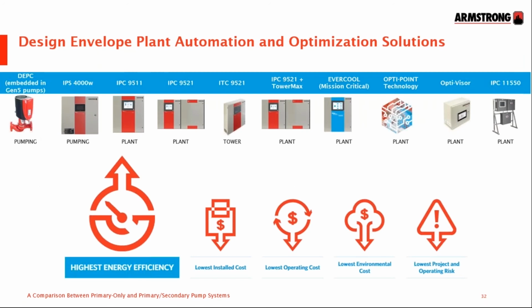Armstrong's range of control products starts with our Design Envelope pumps with the Design Envelope pump controller, which provides sensorless speed control and can also open and shut bypass valves in simple single chiller installations. We've talked about the IPS 4000 in depth, the IPC 9521 for water-cooled chiller plant, and the IPC 9511 for air-cooled chillers. The ITC 9521 is for systems where the cooling tower is the main cooling source of supply, say, for example, water source heat pumps.